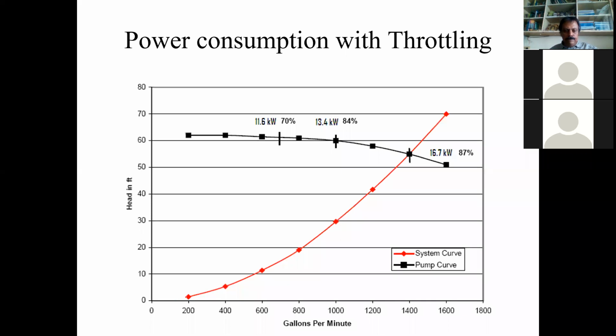Here is a case with throttling. Initially it is operating at this point, maybe 1,400 gallons per minute. This is full speed at this flow. This is the power, 16.7 kilowatt. Efficiency of the pump is 87. Then we throttle. We want only 1,000 gallons per minute, so we throttle it and get 13.4 kilowatt. Efficiency slightly drops. We now want 700 gallons per minute. At 700, we throttle further. Power consumption is 11.6 kilowatt. Efficiency is dramatically down, 70%. So imagine we are putting a VFD on this pump.